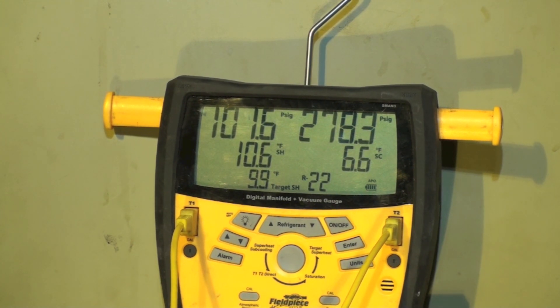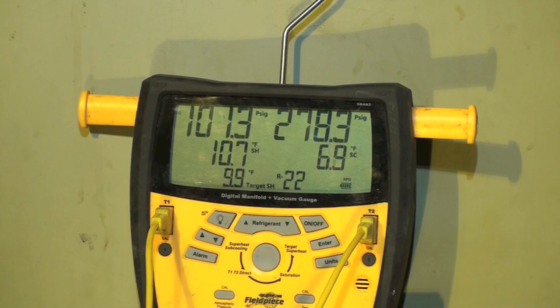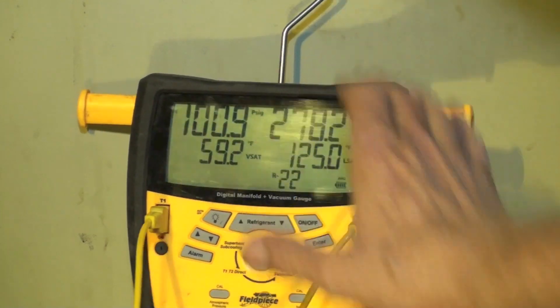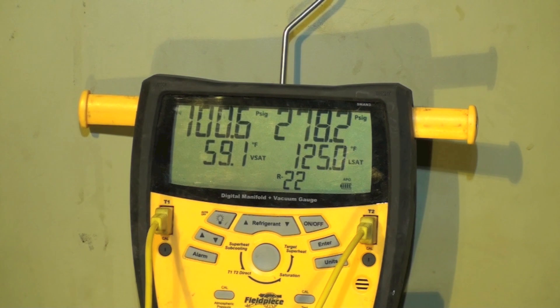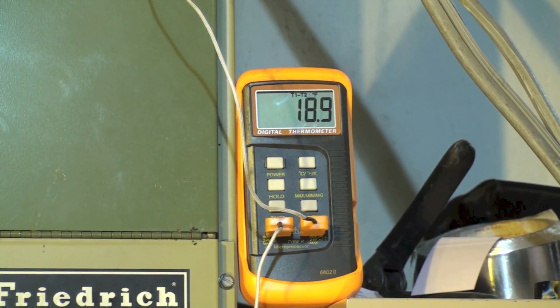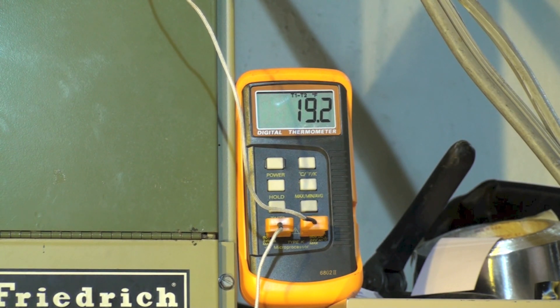Let's look at some final numbers here. I've got 101 on my suction side, which means the saturated suction is 60 degrees. Condensing temperature is 125, which is only 25 plus ambient — not too bad. Looking at the split across the coil: 18.9. Of course, it's dropped each time we've added air, and that's as low as I've seen it.